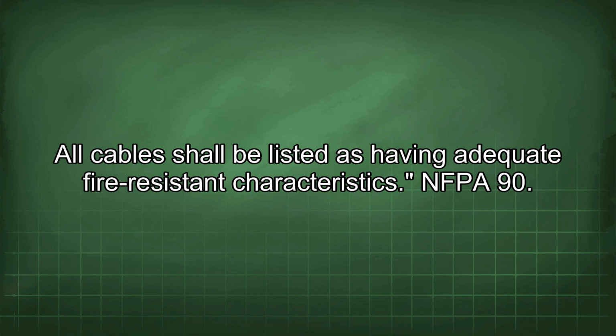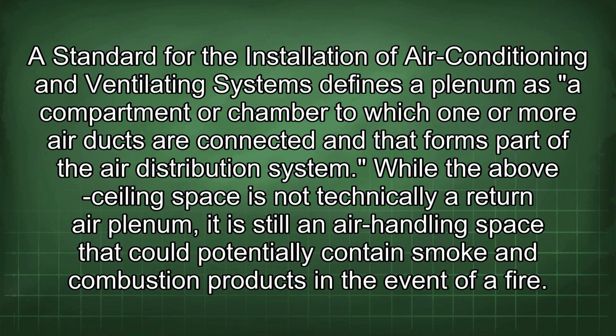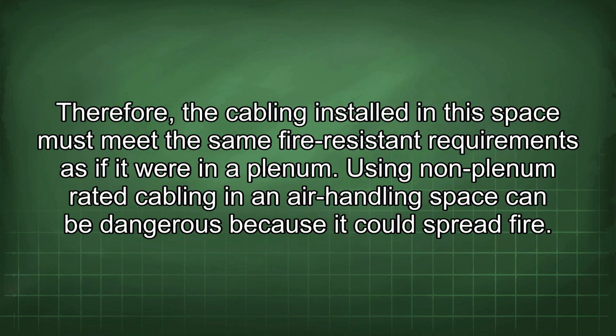NFPA 90A, a standard for the installation of air conditioning and ventilating systems, defines a plenum as a compartment or chamber to which one or more air ducts are connected and that forms part of the air distribution system. While the above-ceiling space is not technically a return air plenum, it is still an air handling space that could potentially contain smoke and combustion products in the event of a fire. Therefore, the cabling installed in this space must meet the same fire-resistant requirements as if it were in a plenum.